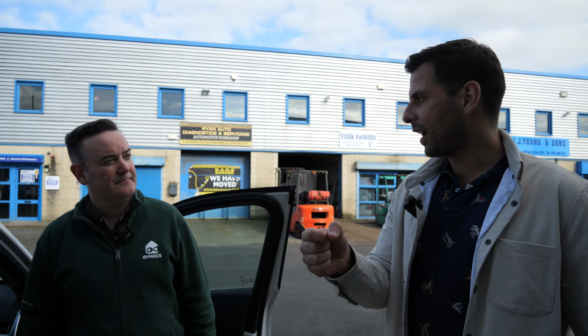My next question was, if I've got an air conditioning unit on a 32 amp breaker, but also on that circuit there's an outdoor light or a socket, will your device monitor that and work to the actual supply rather than just the air conditioning unit? Correct. Generally EVs and air conditioners are supposed to be on their own dedicated supply back to the board, but you're monitoring what's coming into that board.